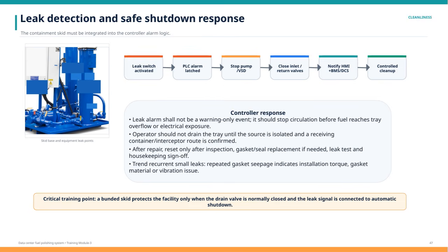This includes stopping the pump or variable speed drive, closing the inlet and return valves to isolate the leak, and notifying the human-machine interface, as well as the building management or distributed control systems. Following notification, the system proceeds to a controlled cleanup process to safely manage any leaked fuel or contaminants. A crucial controller response is that the leak alarm must not be treated as just a warning. Instead, circulation should stop immediately before any fuel can reach tray overflow or cause electrical hazards. Operators should not drain the tray until they have confirmed the leak source has been isolated and there is a proper receiving container or interceptor route available.